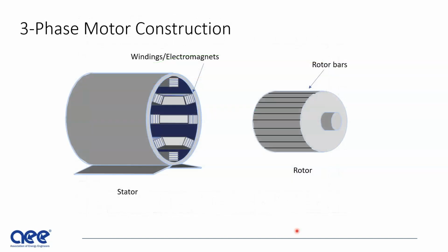Three-phase motor construction. We talked about that copper tube and the ball bearing. Well, they take the place here. We have a stator and we have a rotor core. This is what creates that rotating magnetic field. As you see the poles in the stator, what happens is that the magnetic field is rotated around that stator, and that's what rotates the rotor.